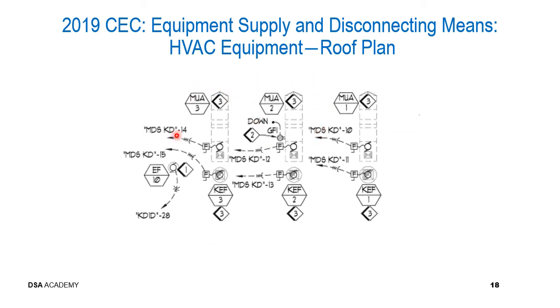Similarly, these other air handling units also have fused disconnects. They all go back to the same panel board, but different circuits. You can see this particular one, air handling unit number 1, goes to circuit 10. This particular one, air handler unit number 2, goes to circuit 12, and this particular air handler unit, its circuit derives from circuit number 14. If we look at the exhaust fans, we have a similar situation in that 3 of these exhaust fans, 1, 2, and 3, also have fused disconnects. They also have designations which show home runs going back to the same panel but different circuits. So it's important to understand what these symbols mean and how to read them.